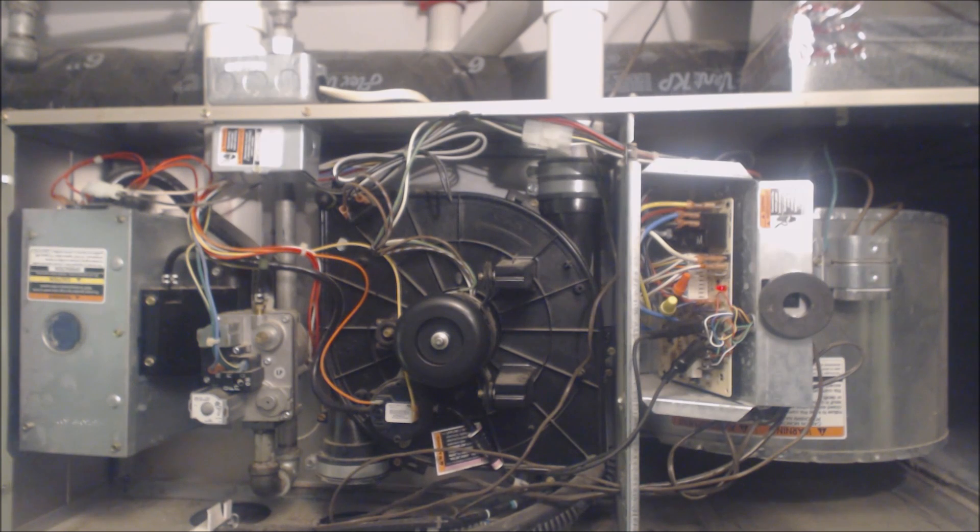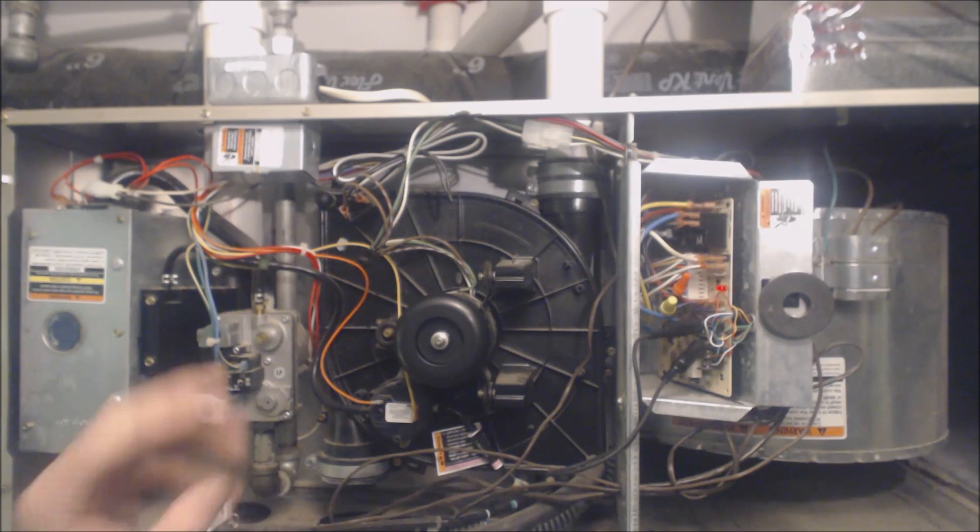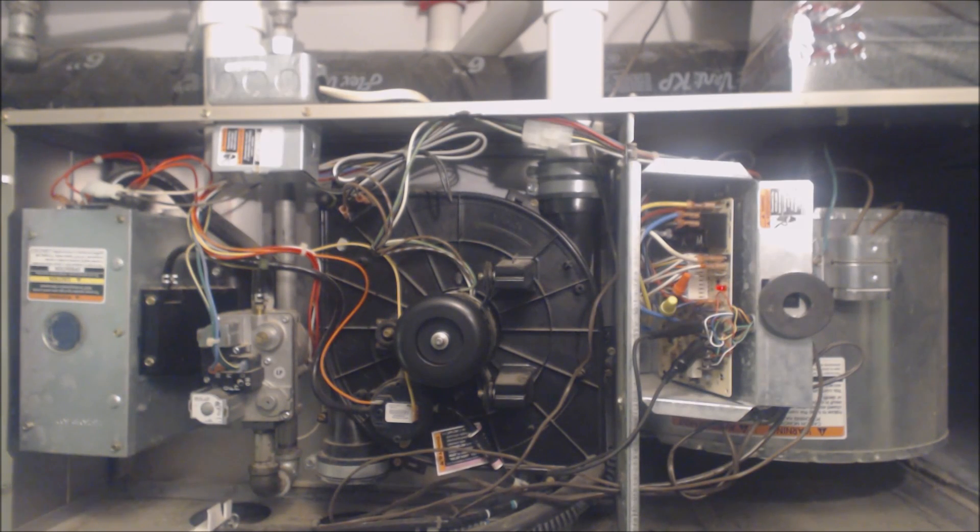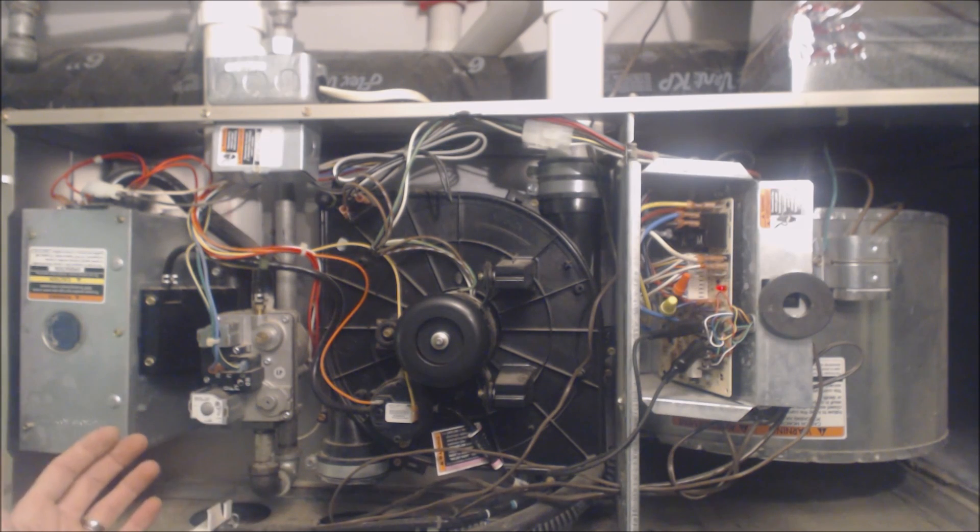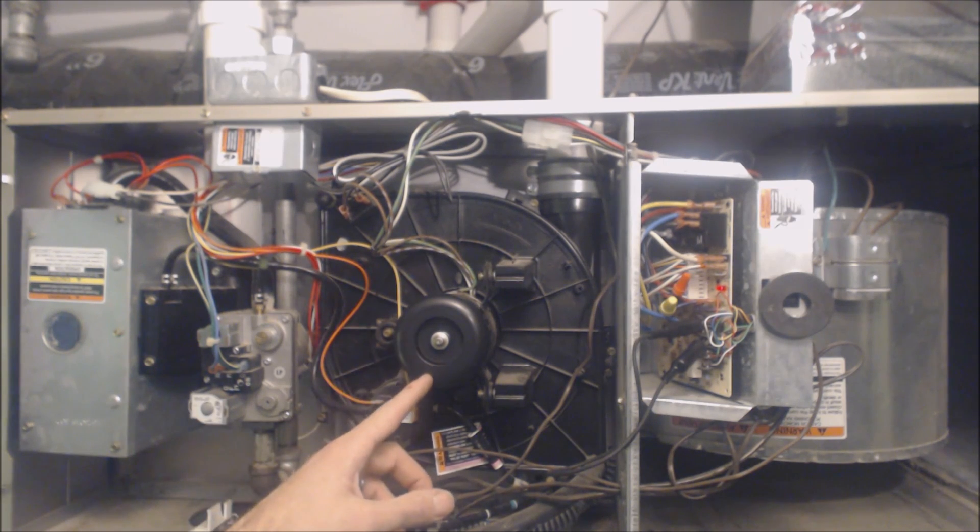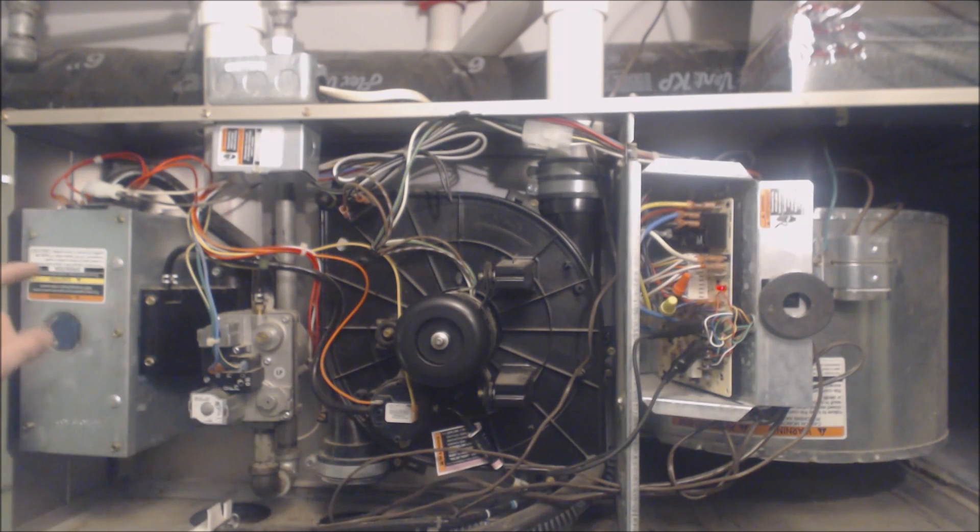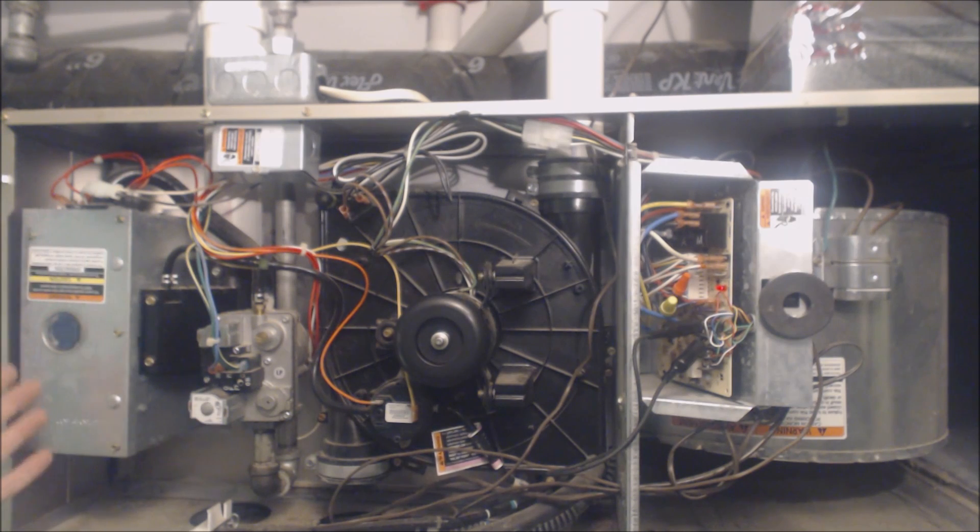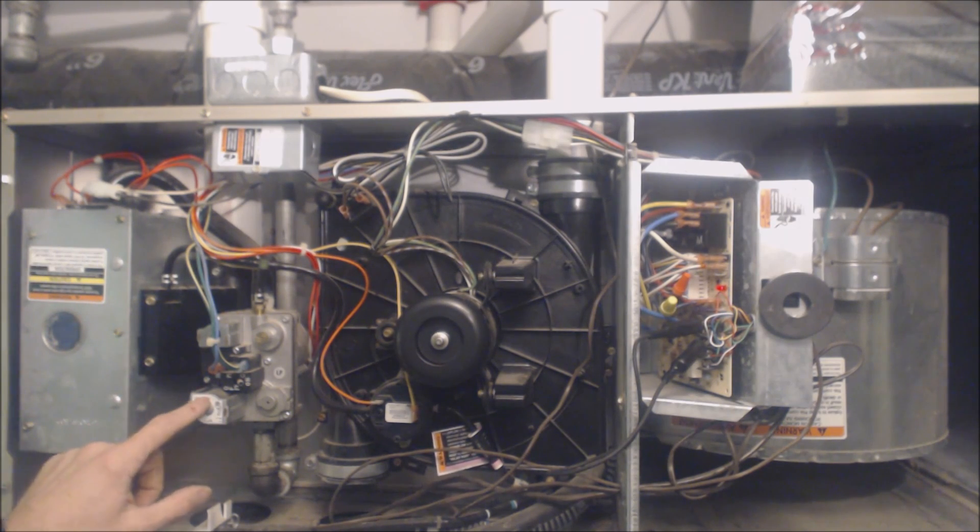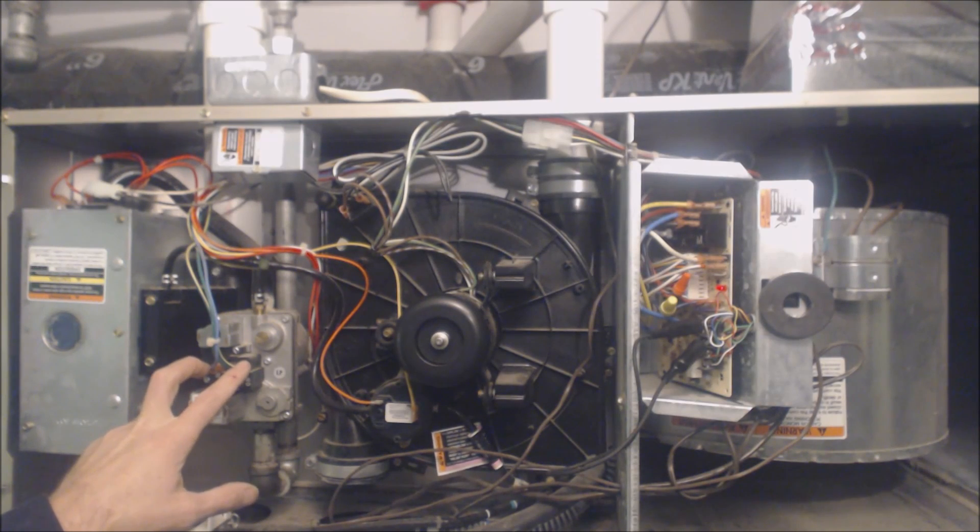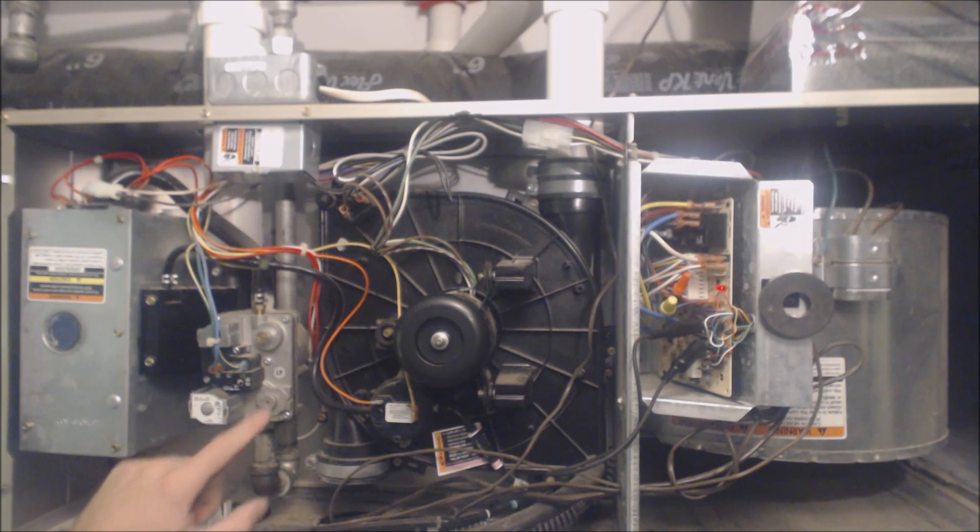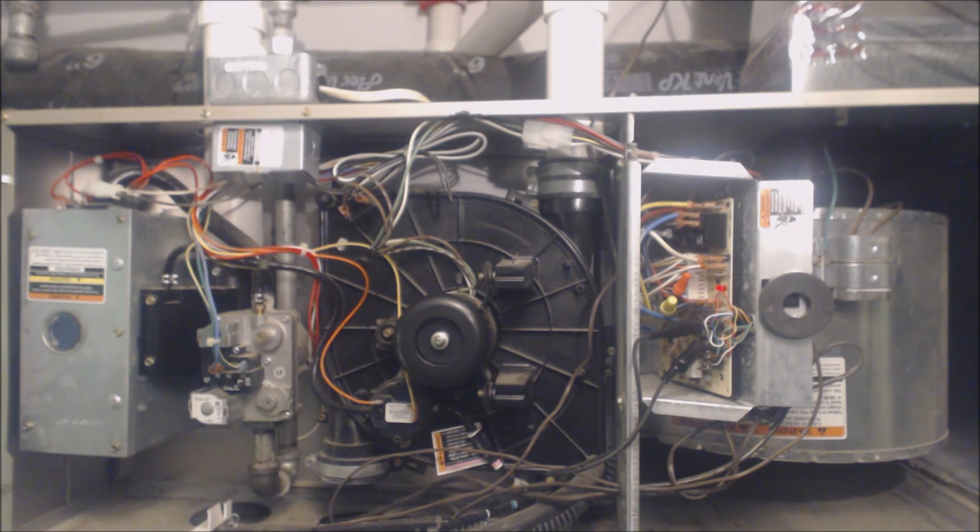You want to know this sequence of operations so that if say three of the steps out of the seven occur, then you know that the fourth one is the problem. For instance, if the inducer motor turns on, the pressure switch closes, the hot surface igniter turns cherry red, and then the gas does not ignite, you know it's something either with the gas valve, the electricity, the 24 volts going to the gas valve. It could be the inlet pressure or it could be what you set the outlet pressure to.